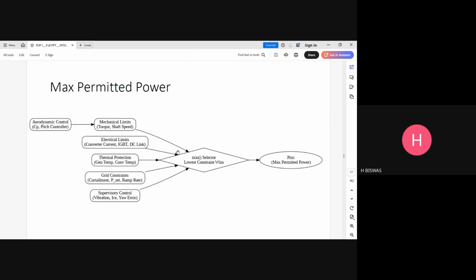If you see this flow chart, on the left hand side it's aerodynamic control, that is power coefficient, pitch controller. On the second column, you see the mechanical limits, electrical limits, thermal protection, grid constraint, and of course SCADA. And SCADA gives you the vibration, ice, yaw error, everything. All together, combined with a selector and lowest constraint wins, that gives you max permitted power. So max permitted power of a wind turbine is contingent upon many other factors, and it's domain specific. There have been mechanical, then electromechanical, and this turbine system. So altogether it comes with how a manufacturer specifies what the max permitted power shall be available.